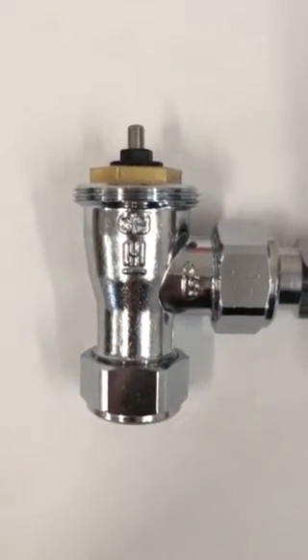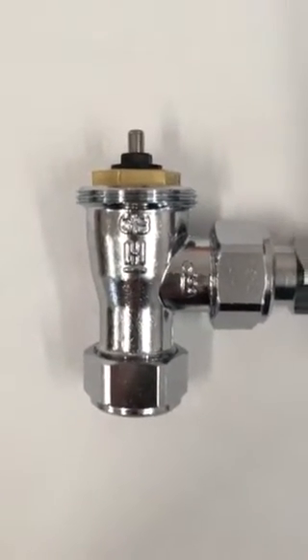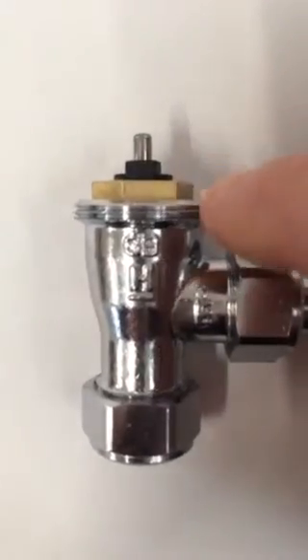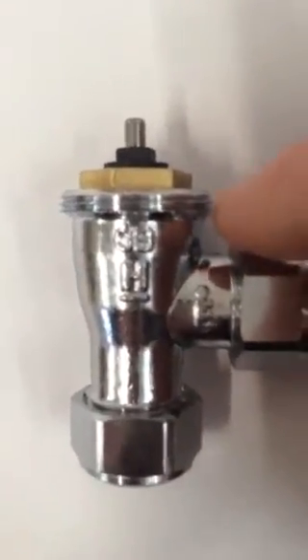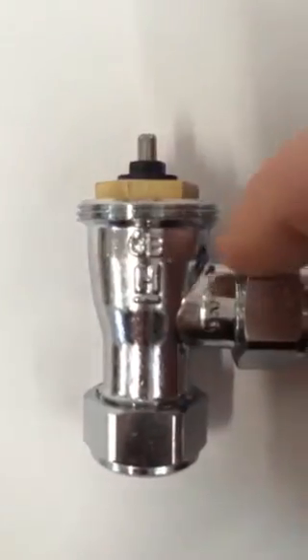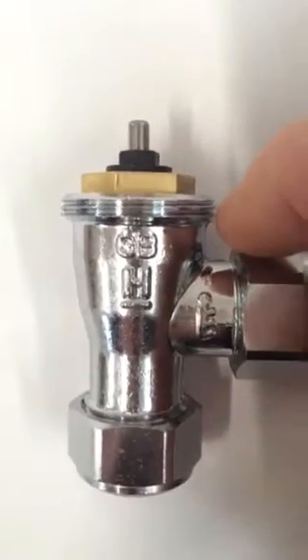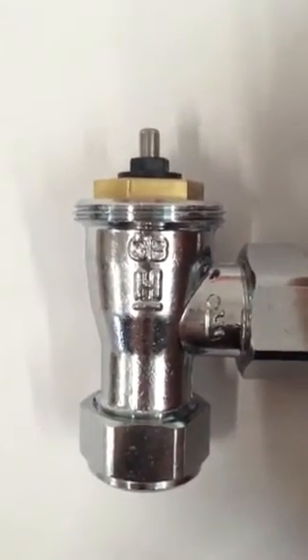Basically, the HN92 valve base plate will only fit certain valves. This is a Honeywell valve. This valve has an M30 by 1.5mm thread, so that means the diameter of the thread is 30mm and the thread pitch — that's the peak to peak — is 1.5mm.